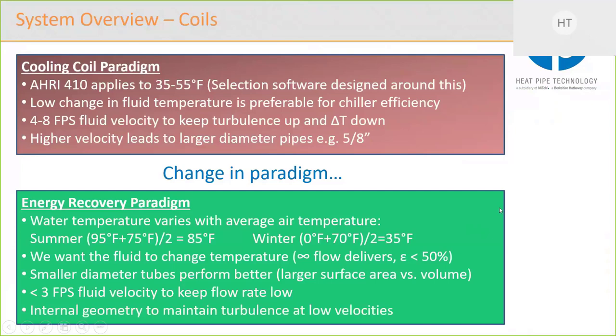What we've done is we've incorporated an internal geometry that maintains the turbulence. So remember I said on the cooling coil, the typical range is 4 to 8 feet per second. We're keeping it below 3, but we've got a special geometry inside our tube that is maintaining that turbulence at low velocities. And that enables it to be more controllable. And that geometry is based on IP that we've developed with our heat pipe coils.